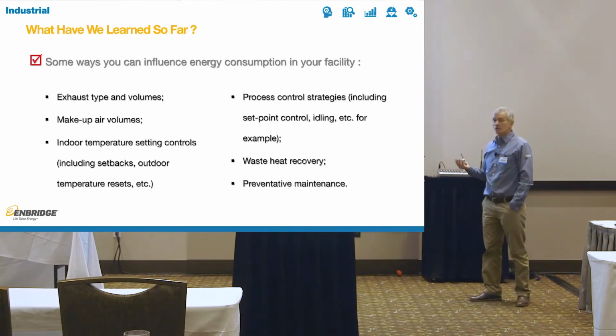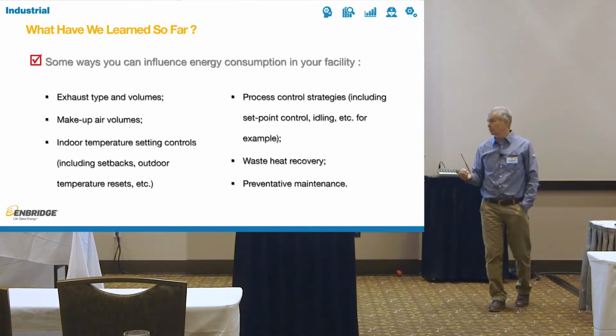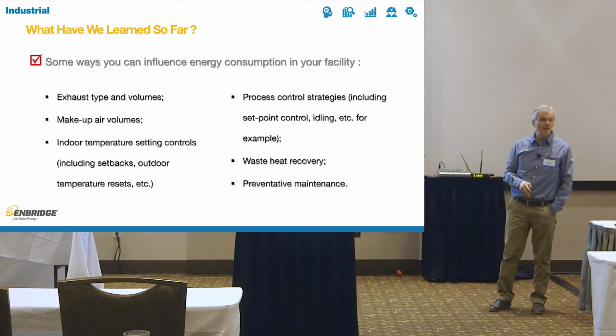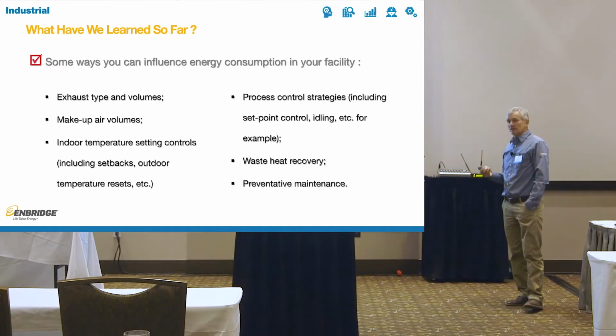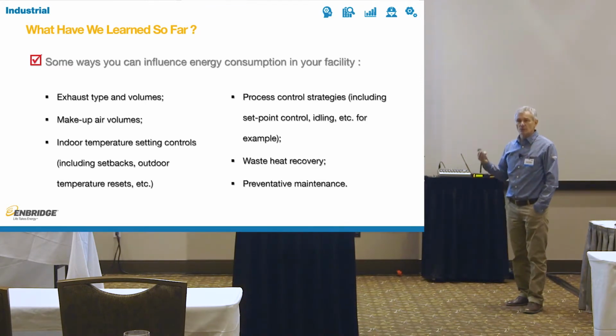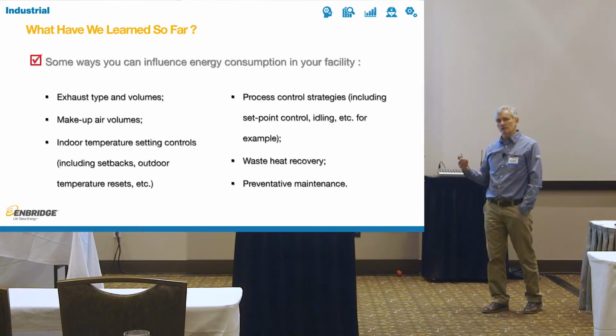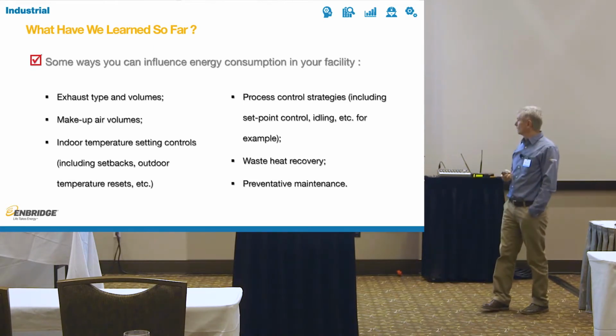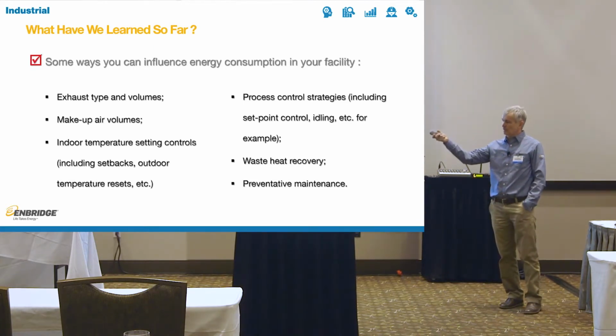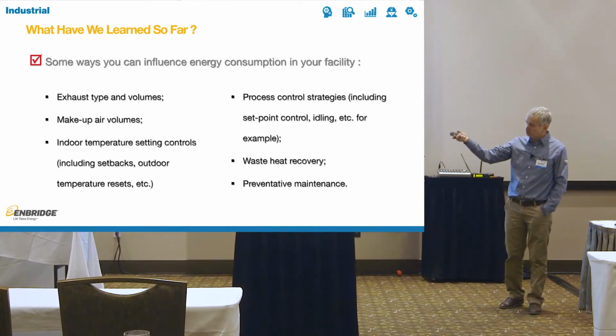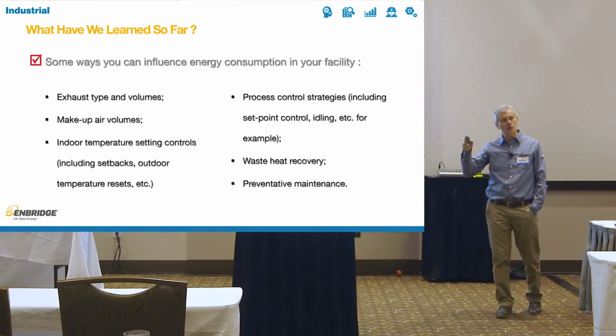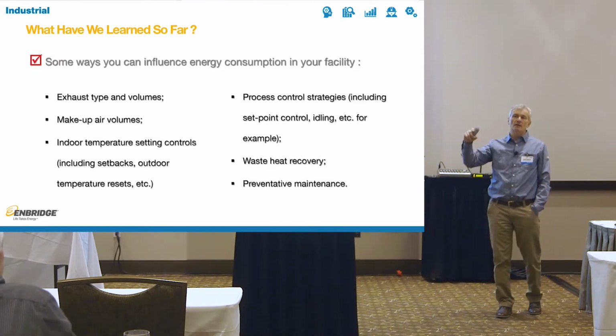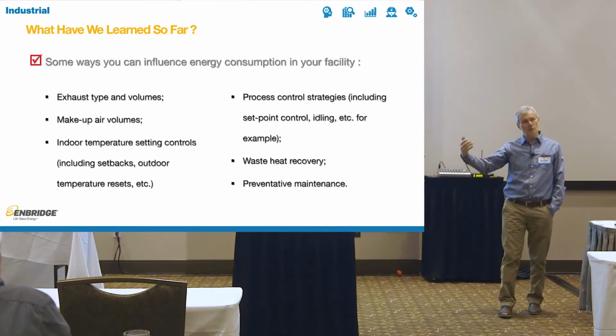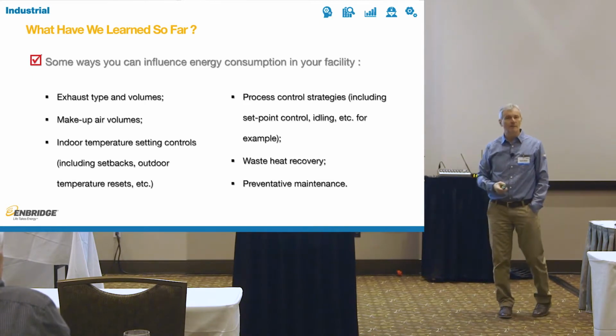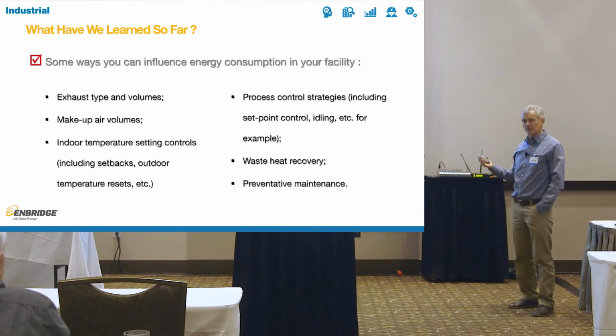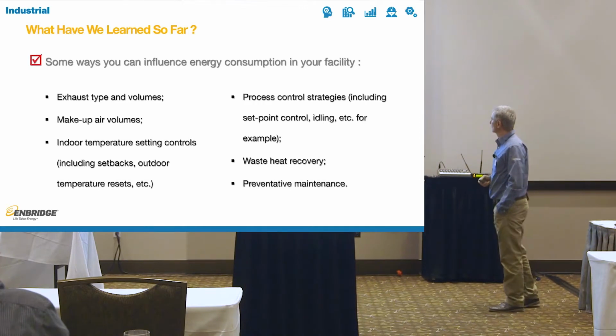Process control strategies. Are you using proper set point controls? Are you going into idling when you can? Waste heat recovery: now you've looked at everything, and all the potential for reducing the waste is used up. Can you recover some of the waste heat? Paul has touched on an example of that, the oven. We had a customer who reduced the oven exhaust, and then they put in a heat exchanger where they preheated the air going back into the oven, and that reduced the load on that recirculating fan. They saved about, I think it was a 1 year payback on a $30,000 investment.